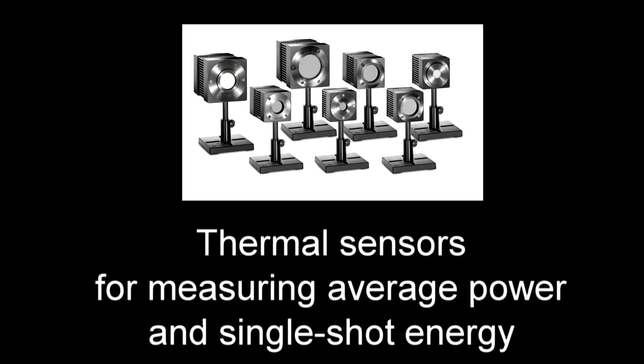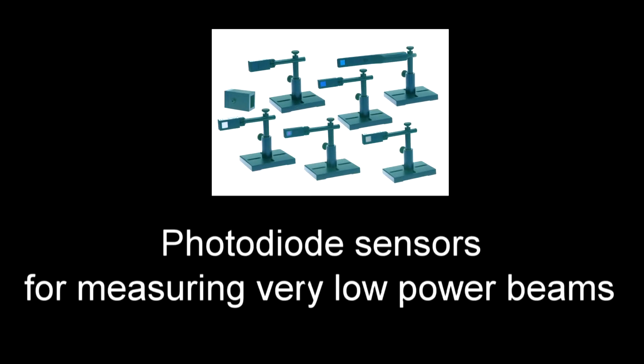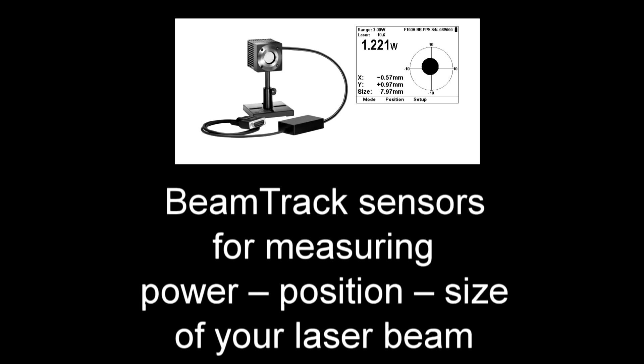One that supports all the new sensor technologies we've introduced, while remaining an economical choice — the new Starlight is that instrument. It supports all standard Ophir sensors, including thermal sensors for measuring average power and single-shot energy, pyroelectric sensors for measuring energy per pulse of repetitively pulsed beams, photodiode sensors for measuring very low power beams, as well as our BeamTrack line of sensors for measuring power, position, and size of your laser beam.